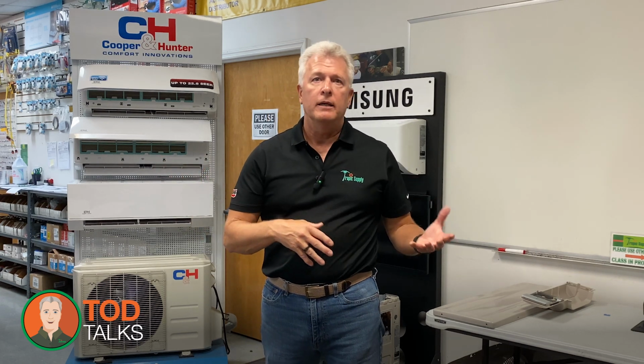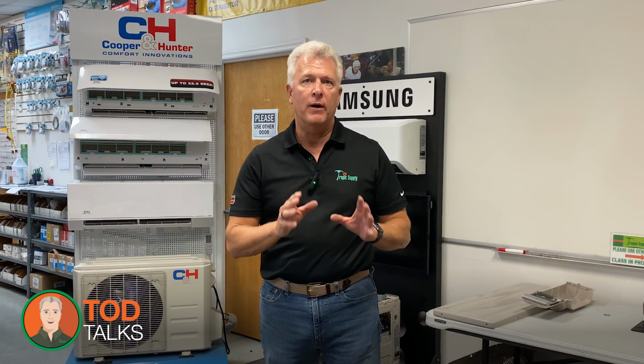Now, you've probably heard terms thrown around like mini split, multi-split, and VRF. Let's clear that up. All mini splits fall under the variable refrigerant flow category, or VRF. They use inverter compressors to control refrigerant flow, which is a fancy way of saying they're super efficient. But when you have multiple indoor units that connect to a single outdoor unit, that's a multi-split. One thing to remember is that unlike the more sophisticated VRF systems, multi-splits require all indoor units to either heat or cool at the same time. They don't have that fancy technology to heat one room while cooling another.